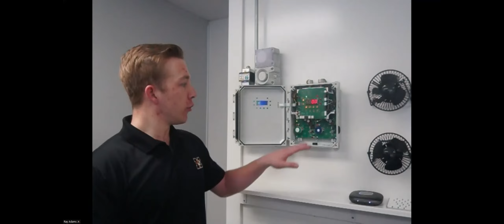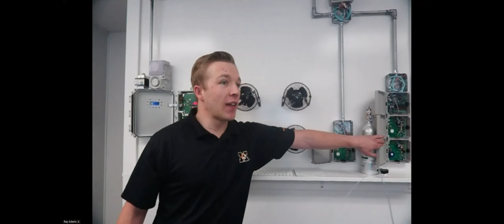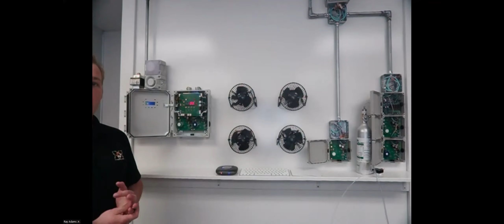Part of what we offer with our standalone unit is that you can have 2 internal sensors as well as 2 remote sensors that tie back into that standalone unit. This saves on raw material cost, since you don't purchase the controls functioning twice, and also on installation, since you don't have to bring fan wiring into 2 separate spots and parallel those dry contacts together. You simply add an extra sensor and tie it back into your standalone unit. We see about a 15 to 20% savings across the industry depending on the other manufacturer. So for applications like firehouses, vehicle repair shops, and car washes, this is really an ideal, cost-effective product.